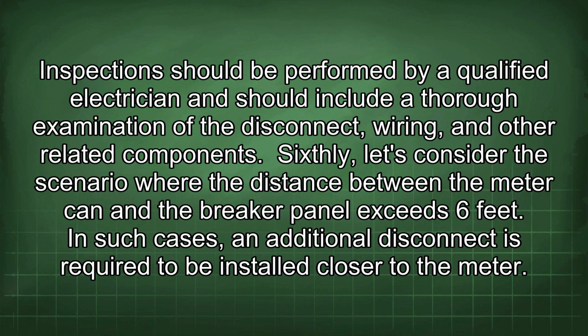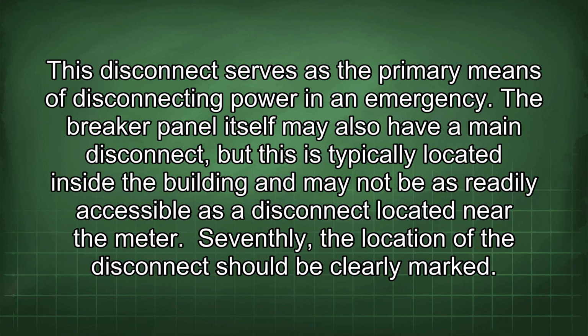Sixthly, let's consider the scenario where the distance between the meter can and the breaker panel exceeds 6 feet. In such cases, an additional disconnect is required to be installed closer to the meter. This disconnect serves as the primary means of disconnecting power in an emergency. The breaker panel itself may also have a main disconnect, but this is typically located inside the building and may not be as readily accessible as a disconnect located near the meter.